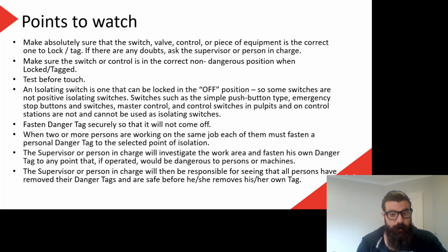I can't lock out every emergency stop switch, so on and so forth. And actually different emergency stop systems might work in different ways. So although I might turn an emergency stop off or even isolate the power to the emergency system, I may still find that there's power on other parts of the circuit that I wasn't aware of. So we should never use any sort of remote control or remote isolating switch or emergency stop or something like that as our isolator, either by switching it off or cutting power to that system and assuming that it's cut power to everything else. If I go into any more detail than that, then with the amount of experience and knowledge that we have now, it probably won't make any sense.